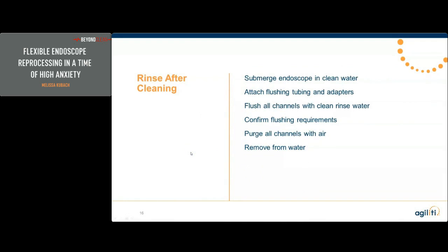Rinse after cleaning: submerge the endoscope in clean water, attach flushing tubing and adapters, flush all channels with clean rinse water, confirm flushing requirements, purge all the channels with air, and remove it from the water.